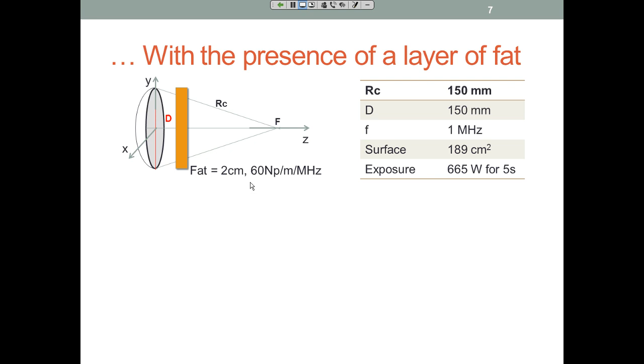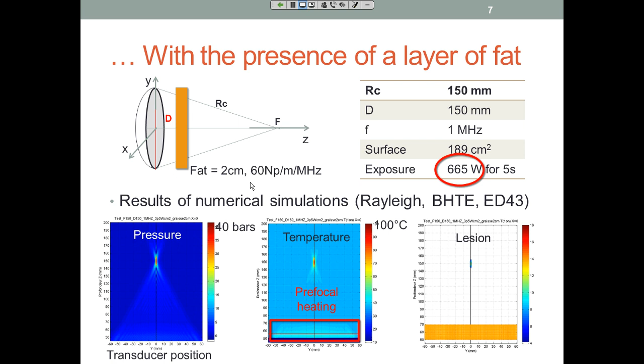So if you run the same simulation, if you want to reach also the 100 degrees Celsius at the focus, what you will get is prefocal heating that can be really problematic. So one solution in that case would be to reduce the dimension of the transducer in order to go beyond this attenuative layer. This is exactly what we are doing, for example, with prostate cancer. So I take the transducer with the same F number, so the ratio between the radius of curvature and the diameter is the same.